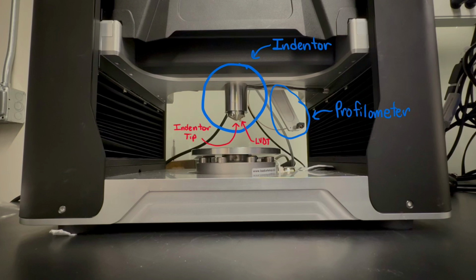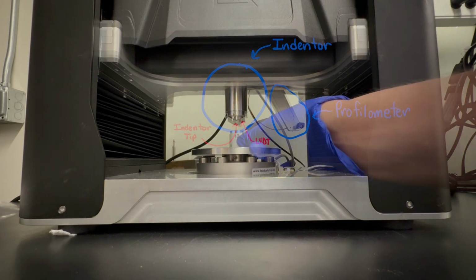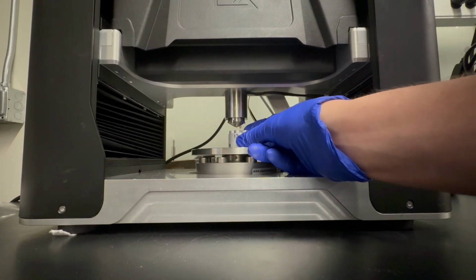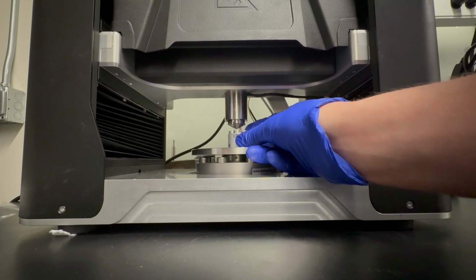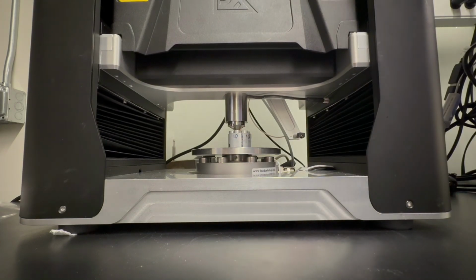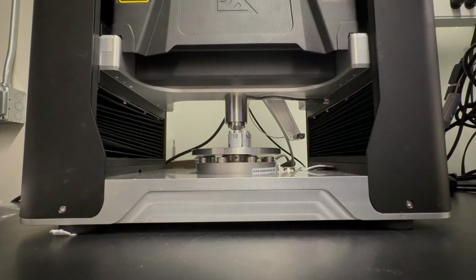And then before placing the sample, it's important to note the parts of the indenter. In the center is the indenter tip, and then to the right of that is going to be the LVDT, which is what is used to sense where the sample is. When initially placing the sample, you're going to want to set it so that the LVDT is directly over the center of one of the samples. This way you can ensure the LVDT senses the sample and it stops.